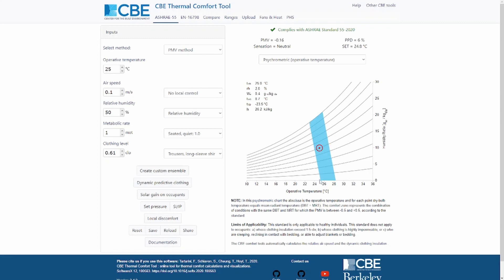In blue, we get the comfort region. The comfort region is defined as between minus 0.5 PMV and plus 0.5 PMV, according to the ASHRAE 55 standard. In this figure, we are assuming that the dry bulb air temperature and the mean radiant temperature are exactly the same.